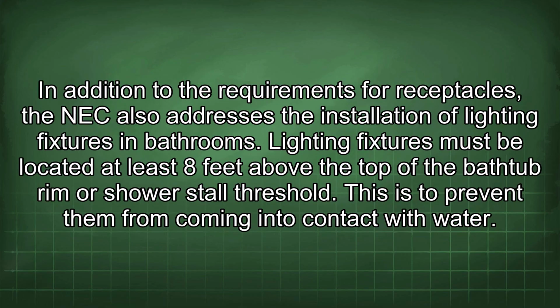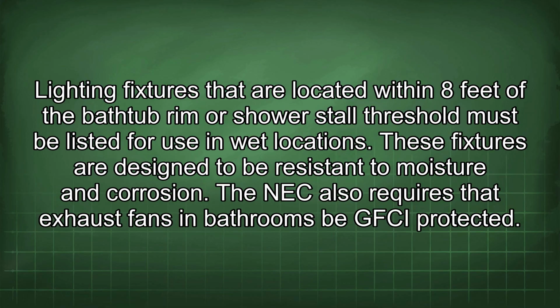In addition to the requirements for receptacles, the NEC also addresses the installation of lighting fixtures in bathrooms. Lighting fixtures must be located at least 8 feet above the top of the bathtub rim or shower stall threshold. This is to prevent them from coming into contact with water. Lighting fixtures that are located within 8 feet of the bathtub rim or shower stall threshold must be listed for use in wet locations. These fixtures are designed to be resistant to moisture and corrosion.